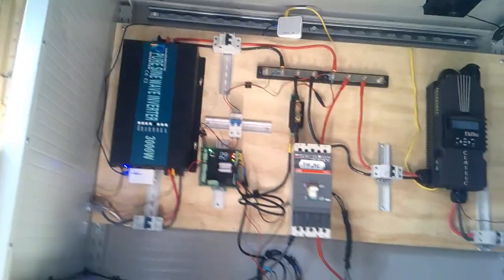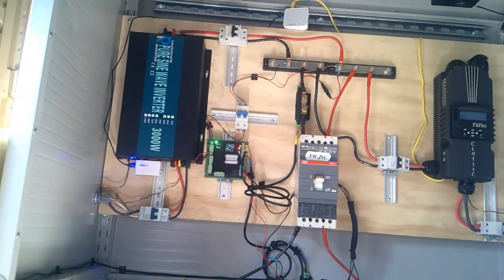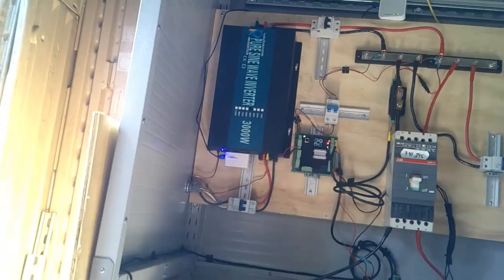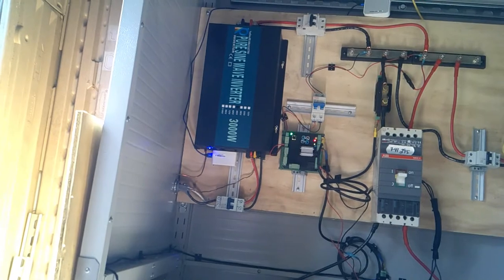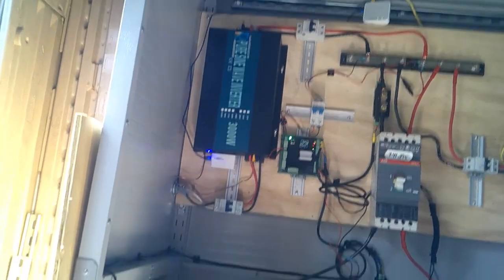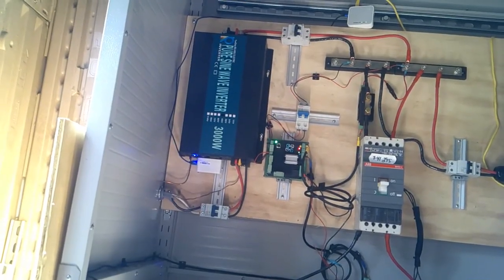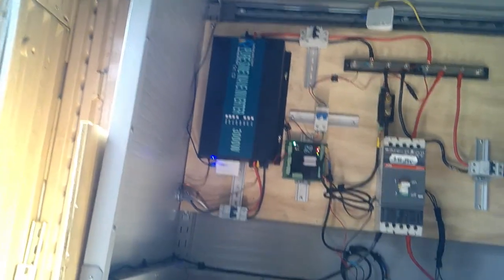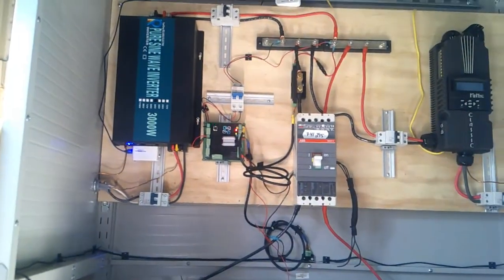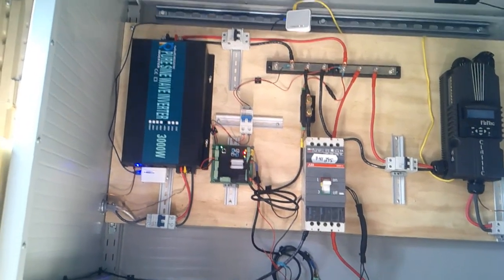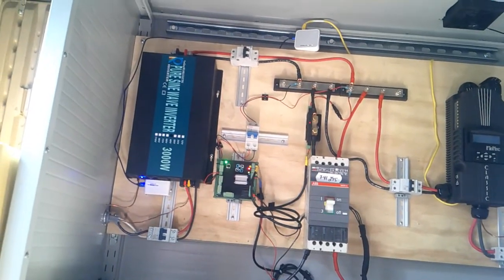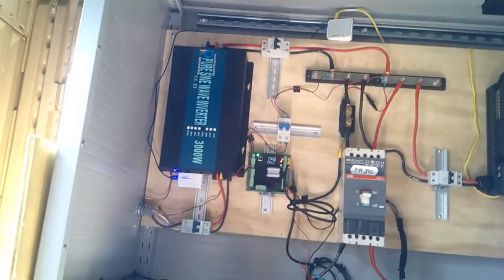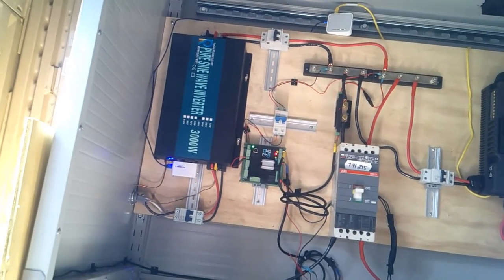Driving the BMS is not so bad but driving the inverter is kind of bad. So what do I have to do? I'm going to have to run the negative leg for the solar charge controller through the center post on the ABB trip. That way when it trips it will shut off the input to the solar charge controller which will shut down the entire system.